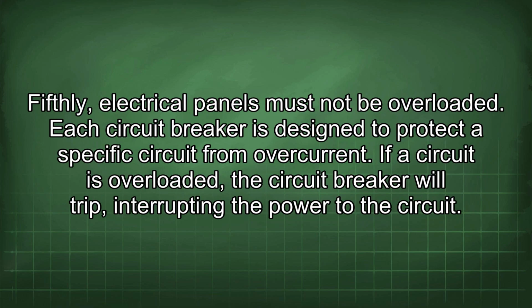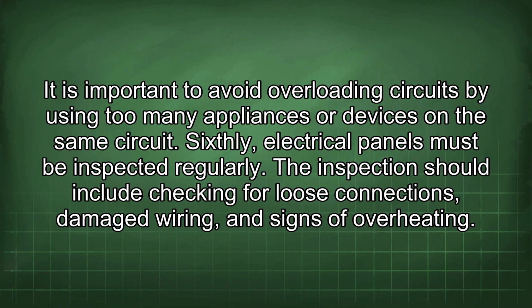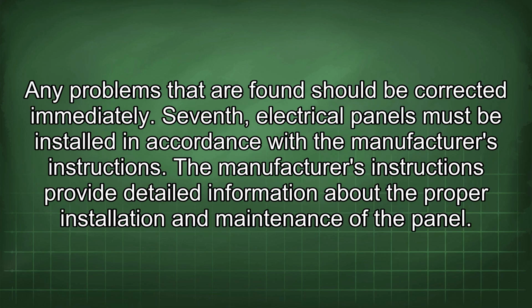Fifthly, electrical panels must not be overloaded. Each circuit breaker is designed to protect a specific circuit from overcurrent. If a circuit is overloaded, the circuit breaker will trip, interrupting the power to the circuit. It is important to avoid overloading circuits by using too many appliances or devices on the same circuit. Sixthly, electrical panels must be inspected regularly. The inspection should include checking for loose connections, damaged wiring, and signs of overheating. Any problems that are found should be corrected immediately.